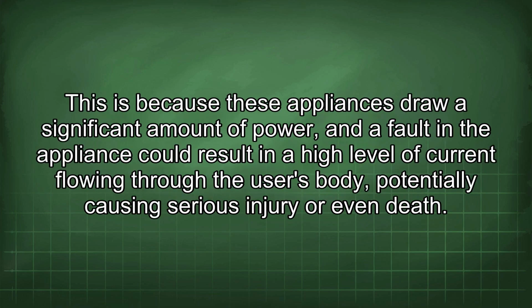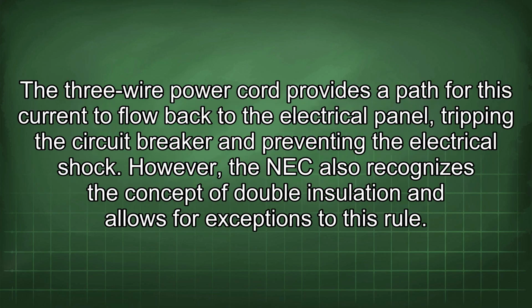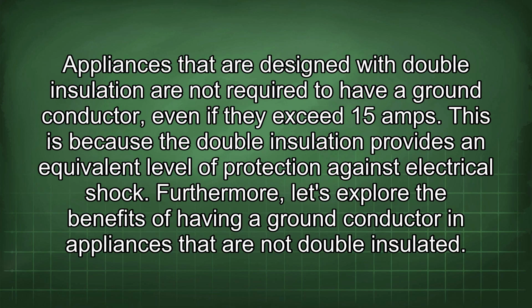This is because these appliances draw a significant amount of power, and a fault in the appliance could result in a high level of current flowing through the user's body, potentially causing serious injury or even death. The 3-wire power cord provides a path for this current to flow back to the electrical panel, tripping the circuit breaker and preventing the electrical shock. However, the NEC also recognizes the concept of double insulation and allows for exceptions to this rule. Appliances that are designed with double insulation are not required to have a ground conductor, even if they exceed 15 amps. This is because the double insulation provides an equivalent level of protection against electrical shock.